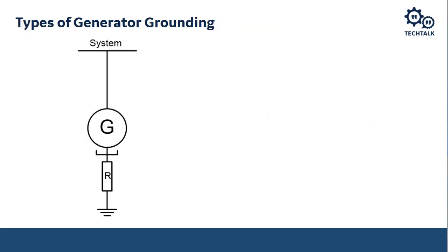The types of generator grounding. One of the more important assets within our industrial system is the generator. How do we protect this generator? How do we ground this generator so we can protect it properly? If we low impedance ground it, it provides a ground source for the system. It can get expensive, however, because we then have to have a resistor that is rated for the ground fault current it is going to be subjected to during a phase-to-ground fault.